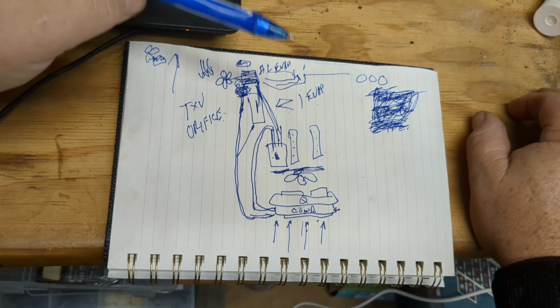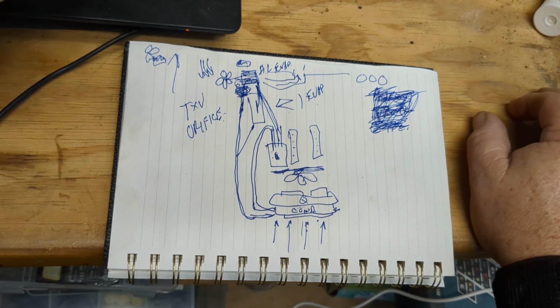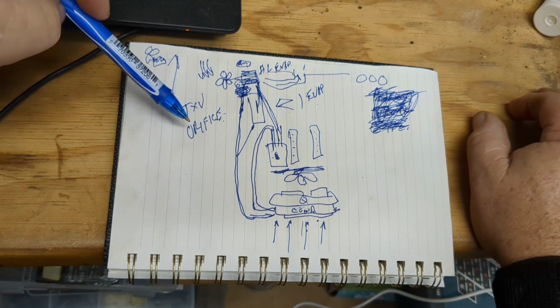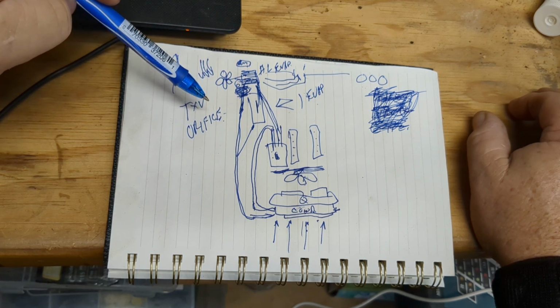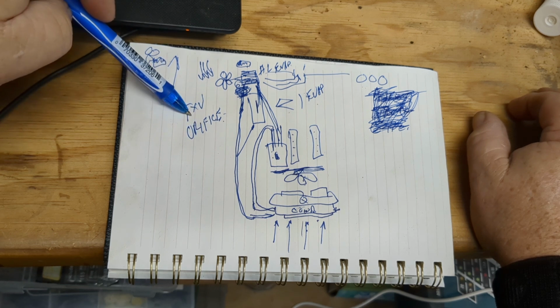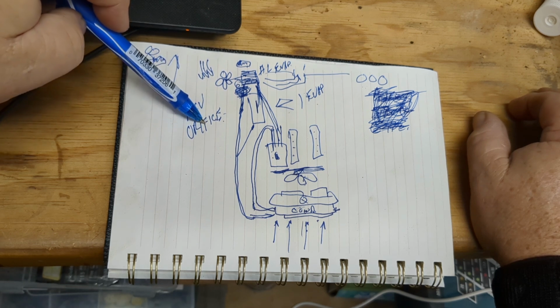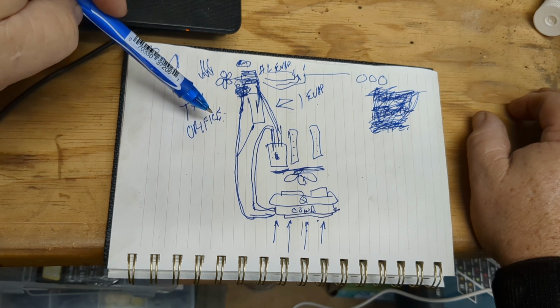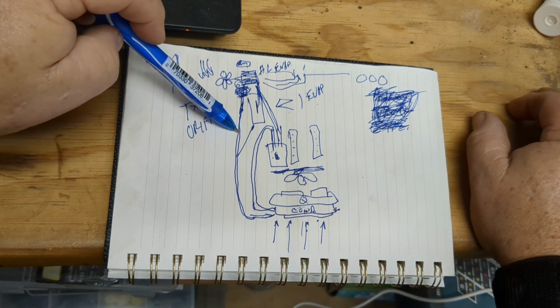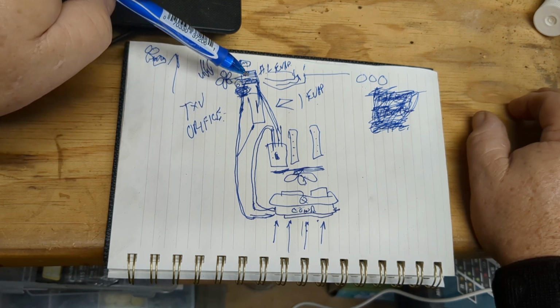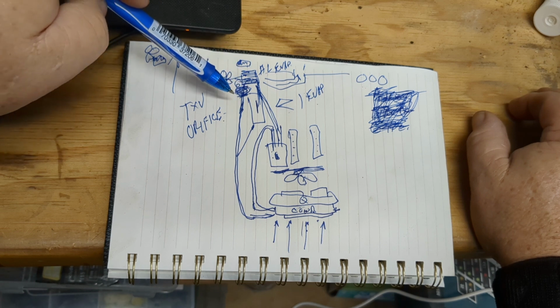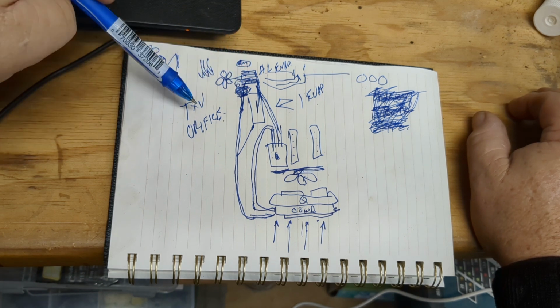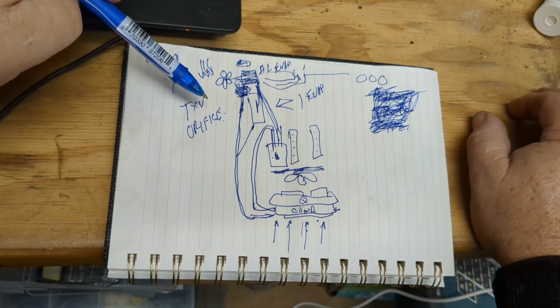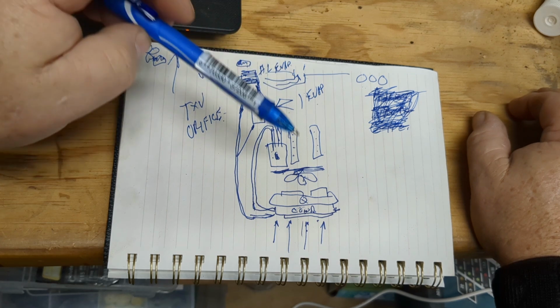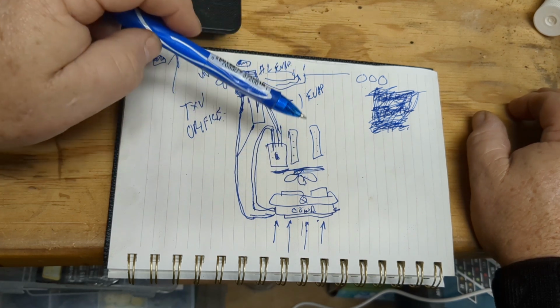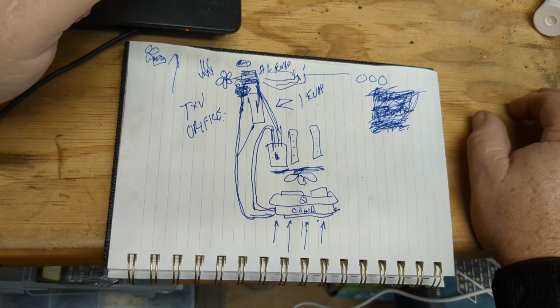From there, you can dial it in a little further. The way that I do that is with the metering devices. I can take these, downsize an orifice, gives it higher atomization, gives it a higher head pressure and atomizes it a little bit quicker, expands a little bit quicker. Or the TXV—really not a whole lot you can do about those, but you can kind of play with that a little bit with your refrigerant charge.